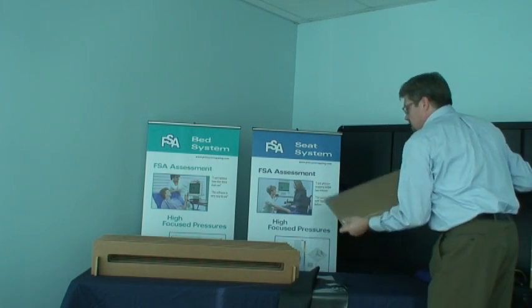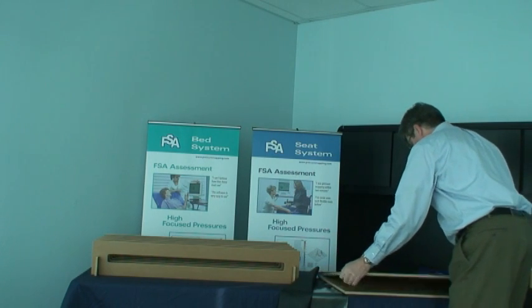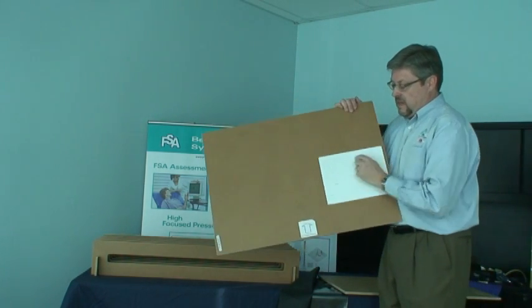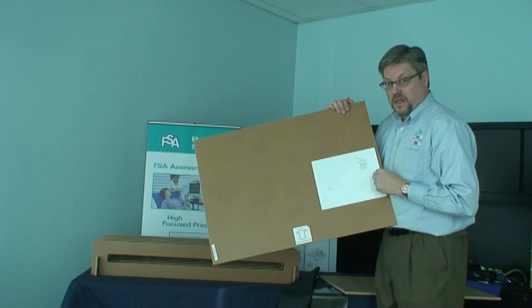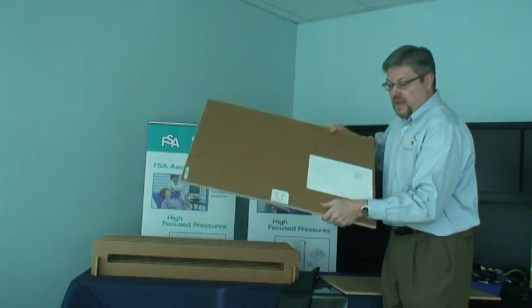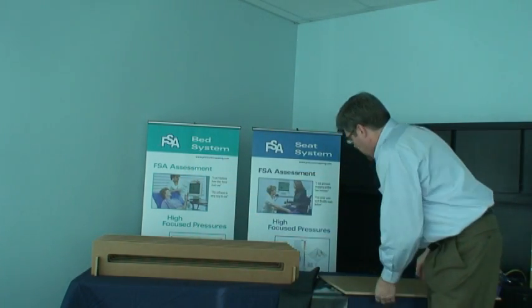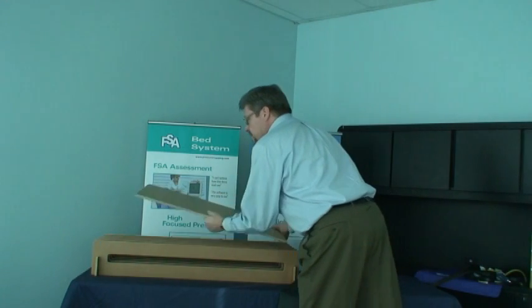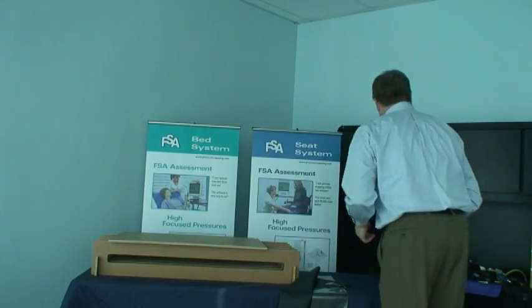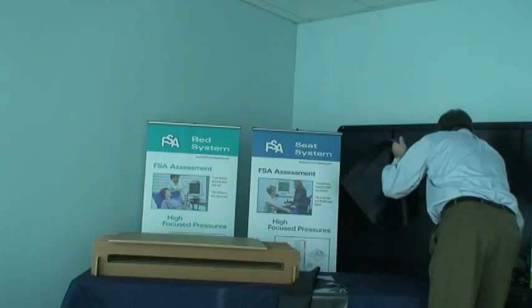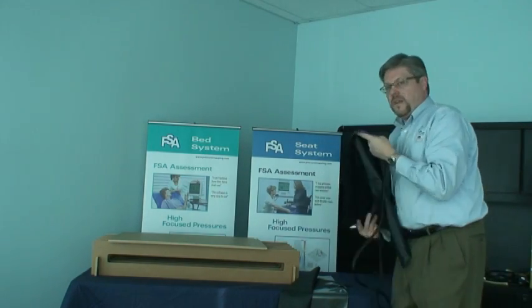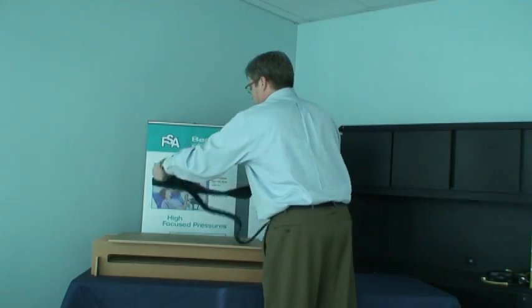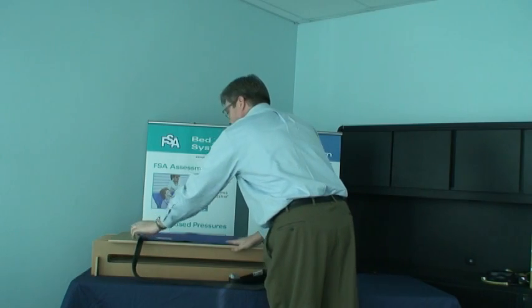To prepare the system for calibration, you take your platens, and you'll notice on the platen itself there's instructions on how to build the calibration frame. This will be the top. You have a bottom platen. To build the assembly, you place that on top of the calibration frame. Then place your seat mat or bed mat.